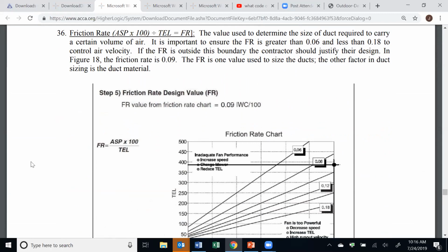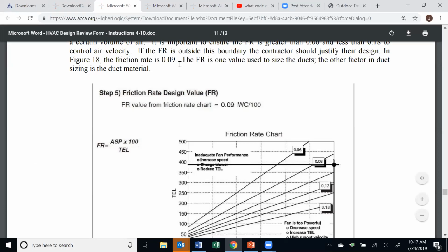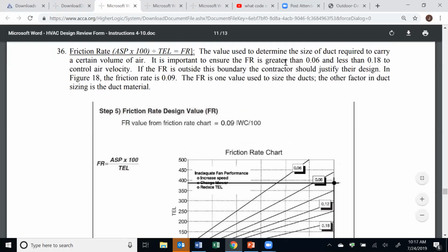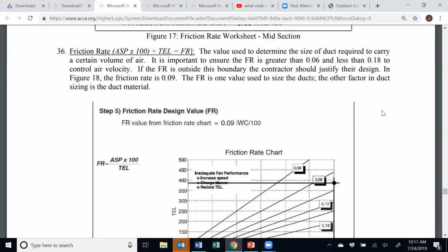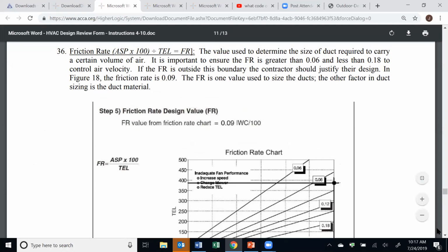so we know from last week's webinar flex duct is the predominant air supply vehicle in Texas. It just is. We are all using it for new residential construction and getting that stuff stretched right and having the friction. So other than the friction rate being greater than 0.06 and less than 0.18, any other thoughts on checking that box number 34's input? And that might be another one to highlight red if it's outside of those parameters. Right. Oh, yeah. That's very good. Let me write that down.